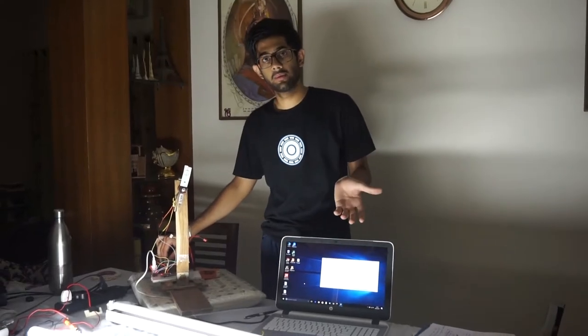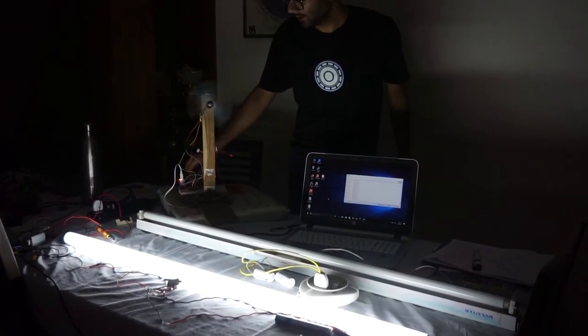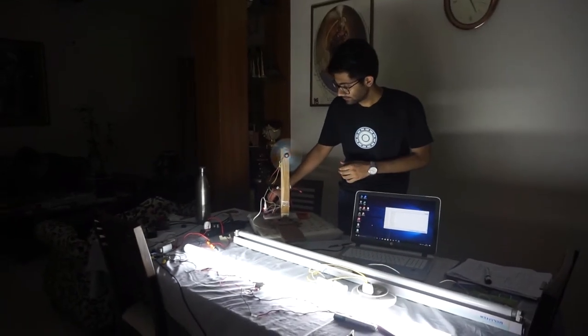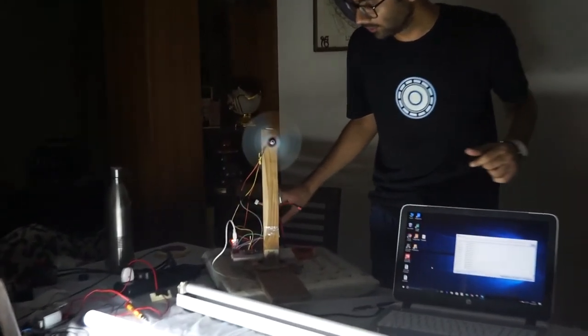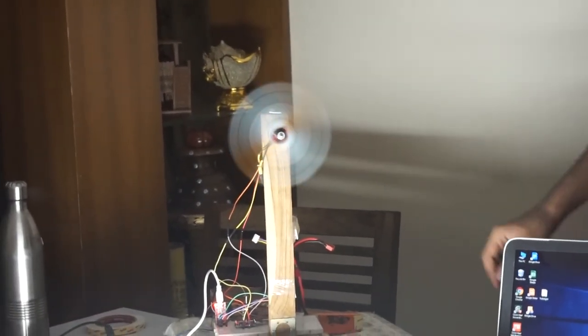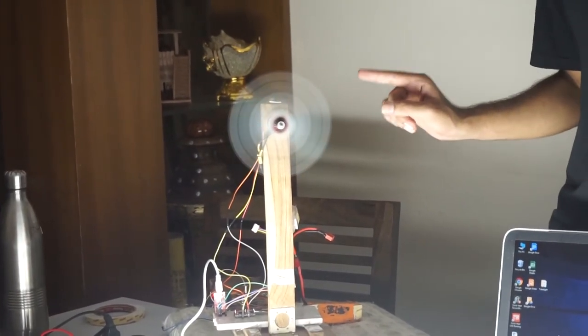Now we will eliminate this stroboscopic effect using a tube light which has capacitors in series. So now there is a normal tube light switched on and we can see the stroboscopic effect. Now I will switch on the other tube light which has capacitor in series. We can see that the stroboscopic effect has been greatly reduced.